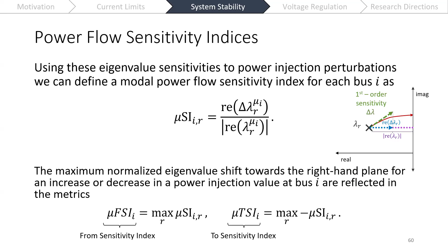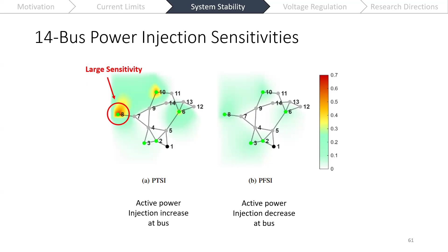Further, then, we define these metrics at a bus level, which are saying, looking over all of these eigenvalue sensitivities, what's the maximum push towards the right-hand plane, normalized by how large the eigenvalue is, for an increase or a decrease in that value. With these sensitivities, if we plot the heat maps of these sensitivities, what we can see is which buses and for what parameters the system is most sensitive to and most likely to potentially become unstable after a perturbation. So here we can see at bus 8, for an increase of active power at that bus, the system is sensitive to that and might become unstable.